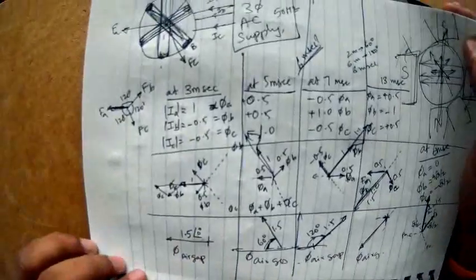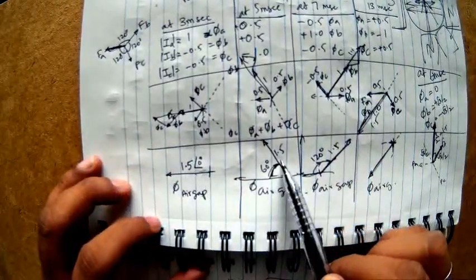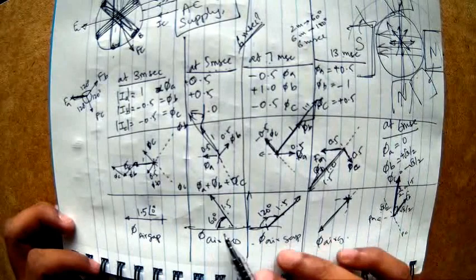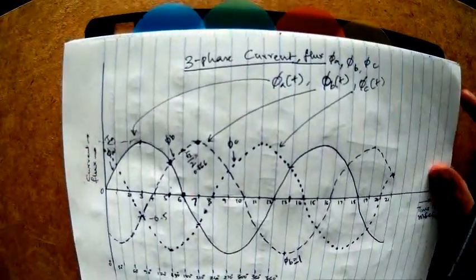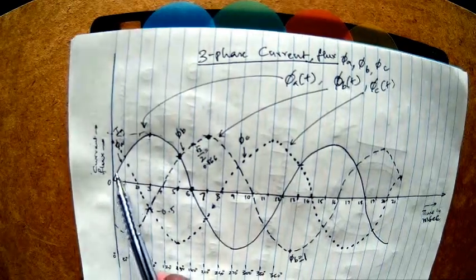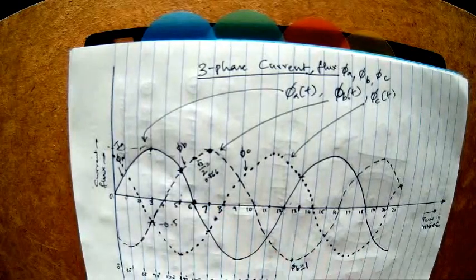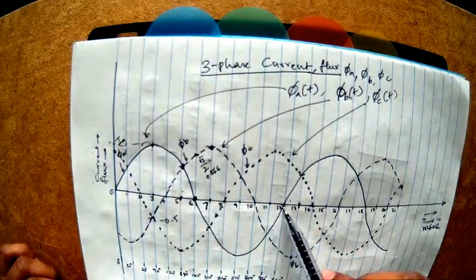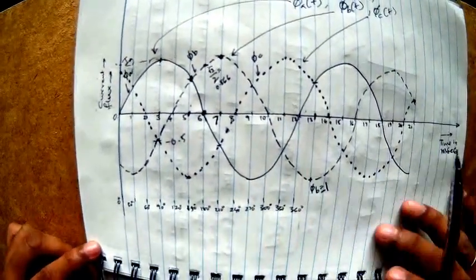If you go back and refer to my previous video, I was saying for every 2 milliseconds the air gap flux is rotating by 60 degrees. Every 1 millisecond the air gap flux is rotating by 30 degrees. If I look at the three-phase currents themselves, you notice that every 1 millisecond represents 30 degrees. So the speed of rotation of the magnetic poles is exactly that of the speed of rotation of your three-phase supply. In other words, if I cover one cycle of my AC supply, the magnetic fields are rotating by 360 degrees.